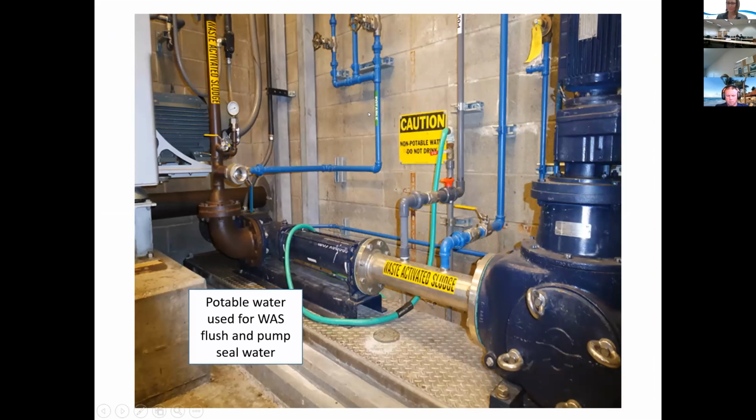This is a fun one. A floor above on here, they used to have an air gap in a tank with a little pump. When they built the place, that's the way it was. But then they added new equipment, and that air gap and tank and pump no longer met the needs of all the new equipment. And so when they were looking to see what to do, they said, well, we have plenty of water upstream of the air gap and tank. So they just got rid of it. They just bypassed it and ran water directly to their waste activated sludge pumps and seal water tanks. Really, really gross. They've since fixed it.